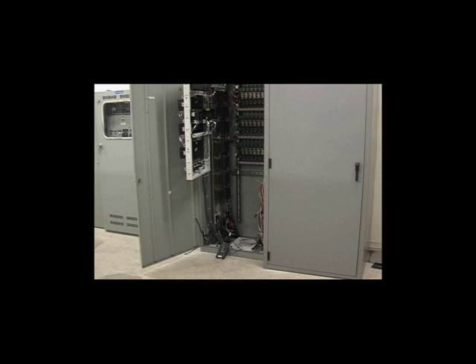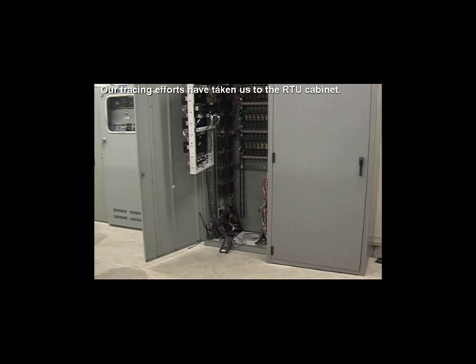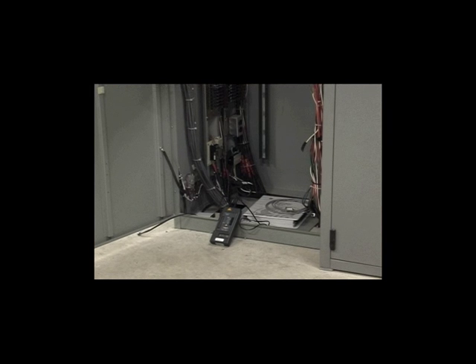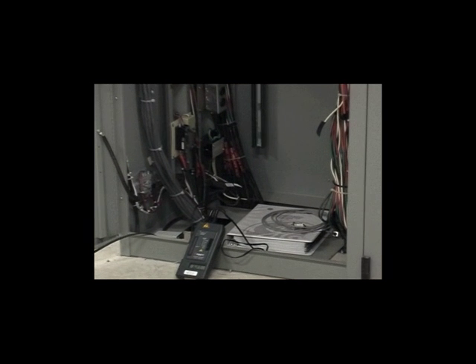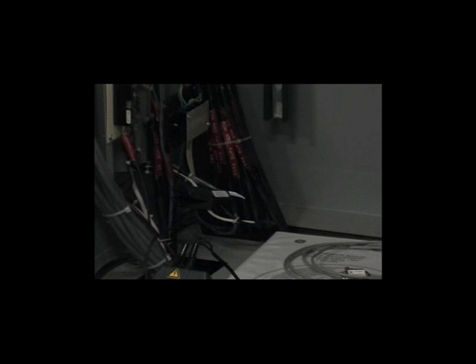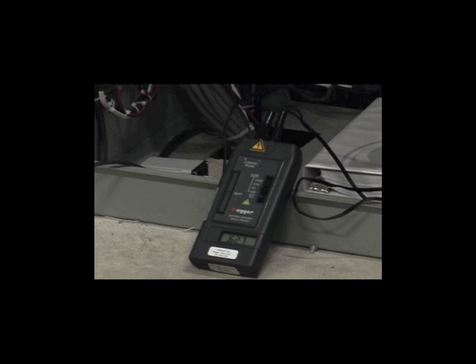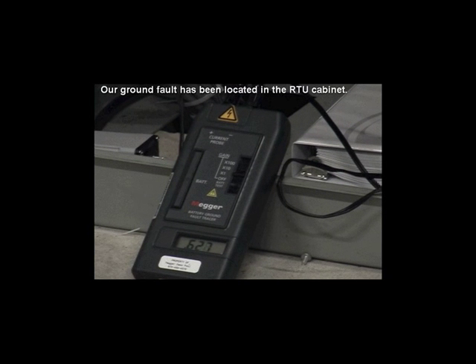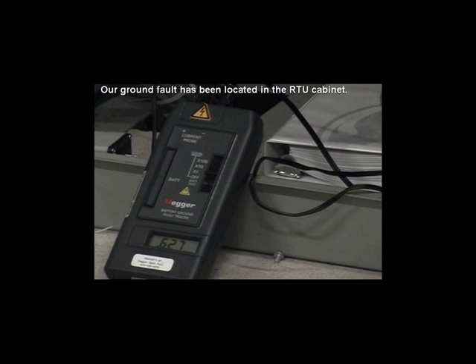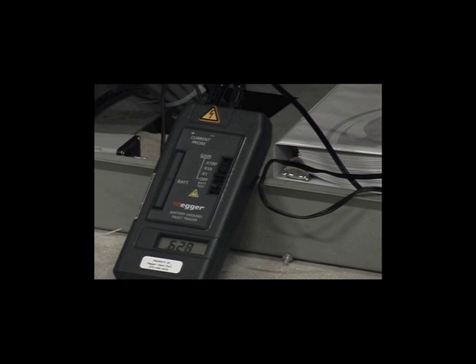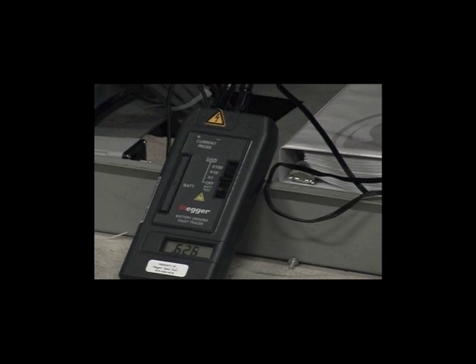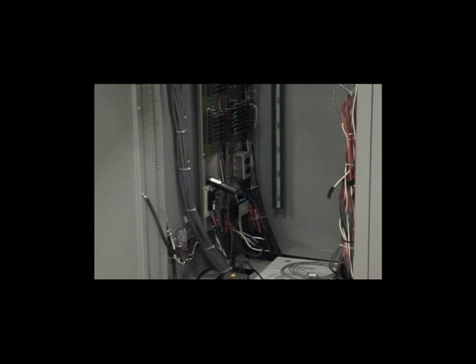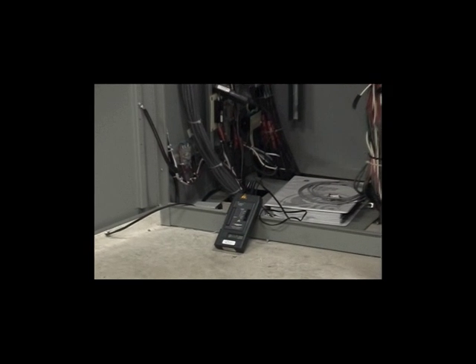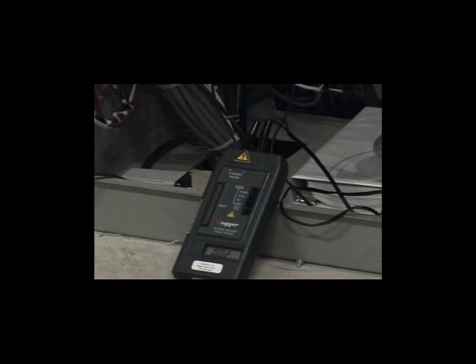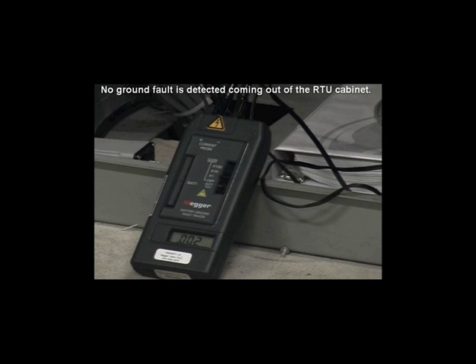Our tracing efforts have taken us to the RTU cabinet. Our ground fault has been located in the RTU cabinet. No ground fault is detected coming out of the RTU cabinet.